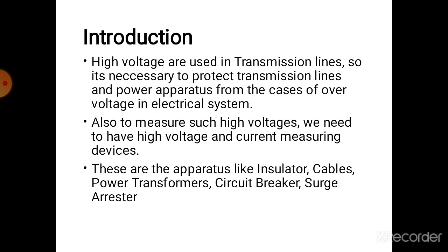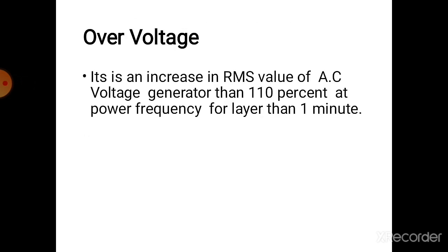It is also necessary to measure high voltage and current. Apparatus involved include insulators, cables, power transformers, circuit breakers, and surge arresters. Overvoltage is a voltage that exceeds the maximum value of operating voltage in the electric circuit, and it increases the RMS value of AC voltage greater than 110 percent of power frequency for more than one minute.